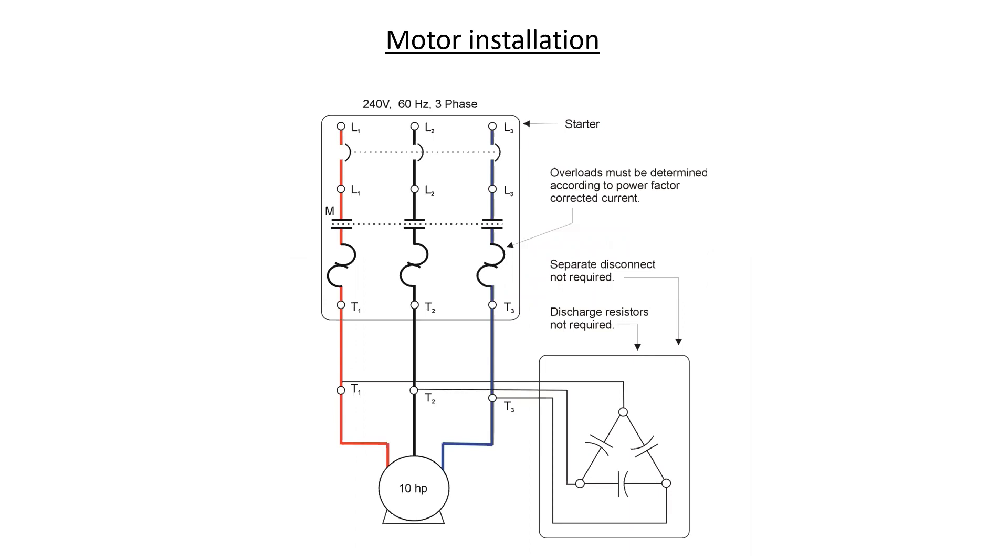Specifically, when capacitors are connected to a three-phase motor right at the terminal box, we don't have to have a disconnect, nor do we need discharge resistors. And that's because when the motor is turned off, the capacitors will discharge through the motor winding itself.